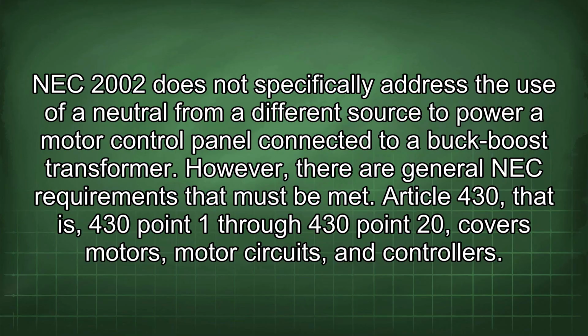NEC 2002 does not specifically address the use of a neutral from a different source to power a motor control panel connected to a buck-boost transformer. However, there are general NEC requirements that must be met. Article 430, that is 430.1 through 430.20, covers motors, motor circuits, and controllers.